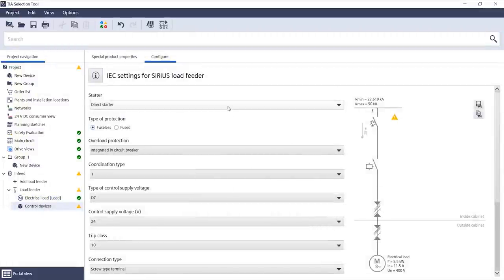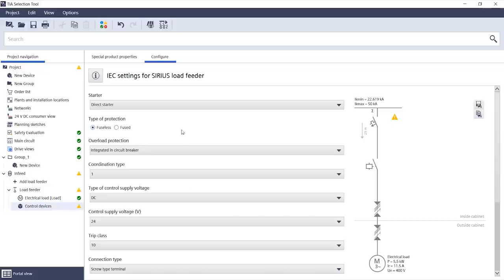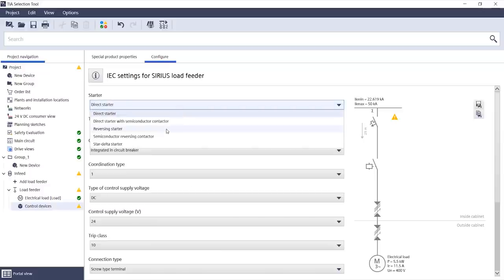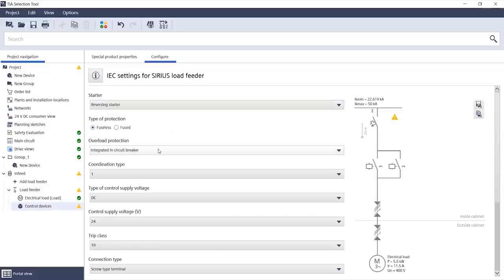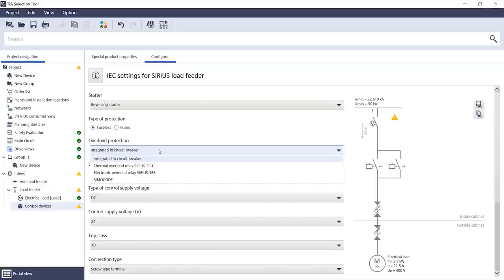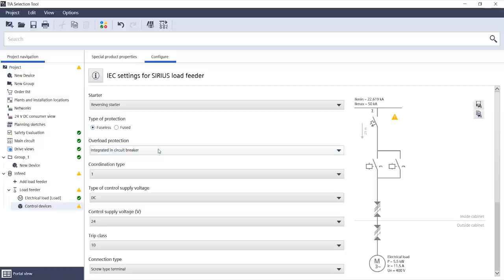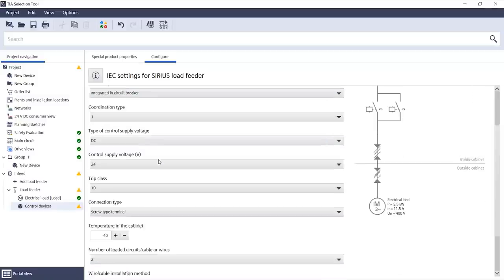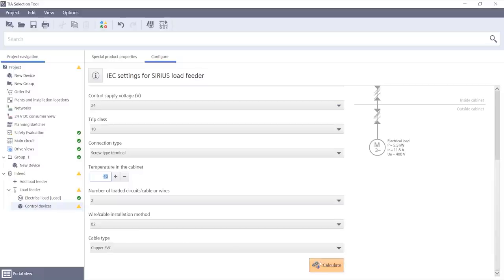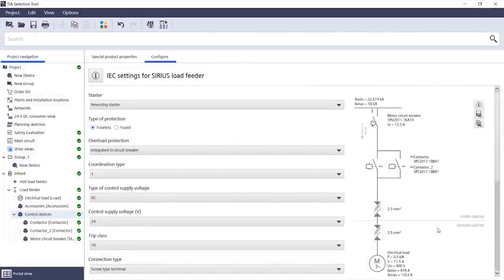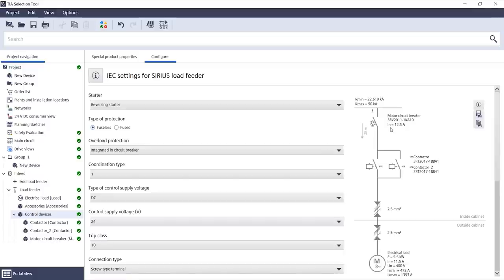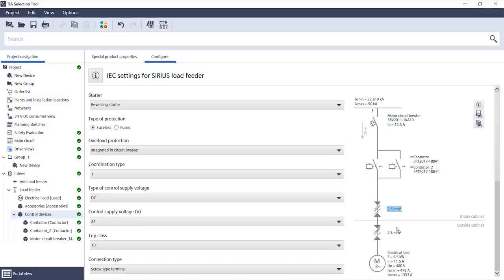Let's continue. I select the switching devices and dimension them. My first and most important step is to specify the start type here. And then I can select the overload protection which I want. When I'm done, I can have everything calculated with the push of a button. And I can already see the results in the single line diagram here to the right. The circuit breaker and contactors for the motor and down here the cable cross sections I need to use.